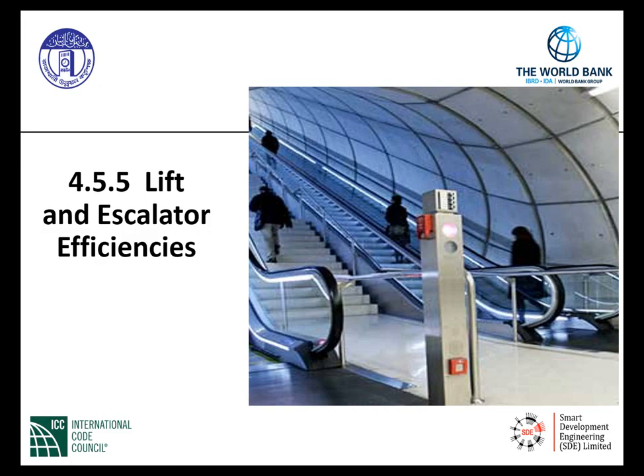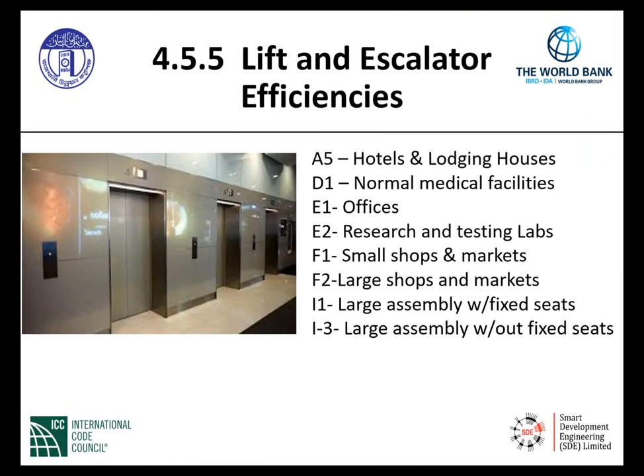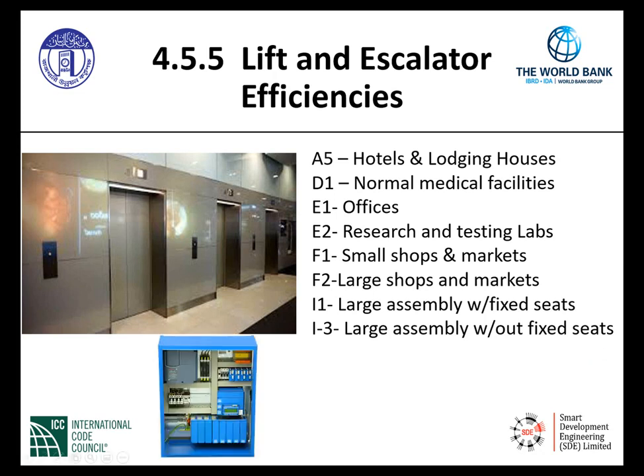When it comes to lifts, to save energy in elevators, section 4.5.5.3 lets us know that the lifts in buildings of occupancies, all of these, the hotels, medical facilities, offices, research and testing labs, small shops and markets, large shops and markets, large assembly with fixed seating, large assembly without fixed seating. Right? So in all of these occupancies, if there's elevators, they have to be provided with controls to reduce the energy demand using certain features if it's a traction drive elevator. So it has to have an AC variable voltage, variable frequency, VVVF, drive on non-hydraulic elevators. What in the world is that?